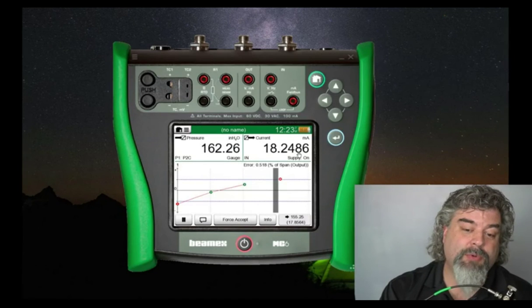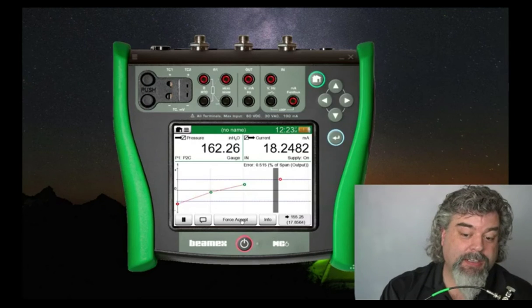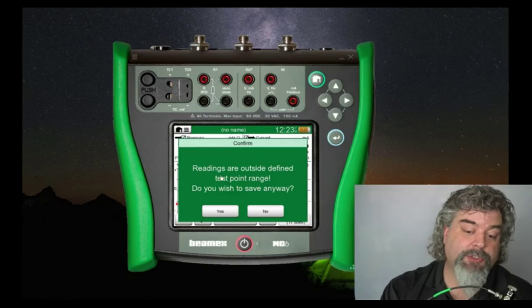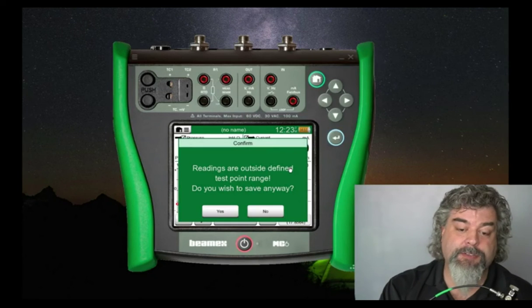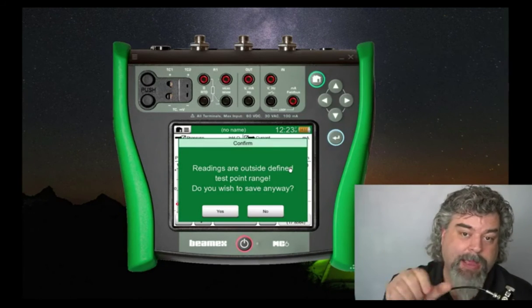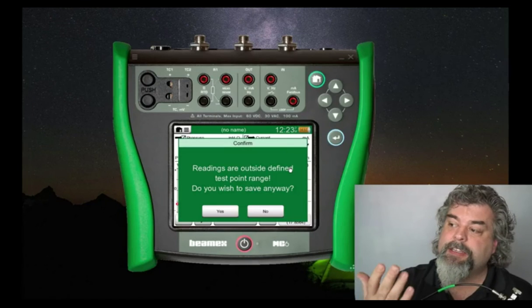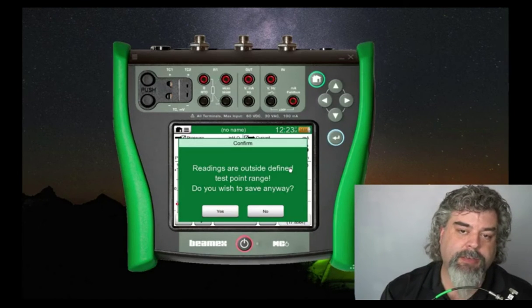At 162.27 inches of water, we're getting 18.2486 milliamps. And I'm just going to accept this right here. I'll choose force accept. It's outside of our little gray bar that we were aiming at, but that's okay. As long as it doesn't violate any of our calibration policies or procedures, this is still a valid measurement.